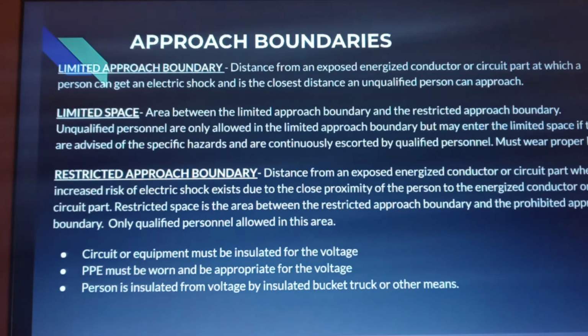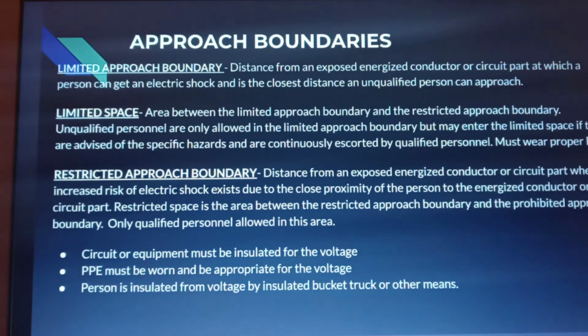The restricted approach boundary is the distance from an exposed energized conductor or circuit part where an increased risk of electrical shock exists due to the close proximity to the energized conductors or circuit parts. Restricted space is the area between the restricted approach boundary and the prohibited approach boundary. Only qualified personnel are allowed in this area, and the circuit or equipment must be insulated for the voltage inside the restricted approach boundary. PPE must be worn and be appropriate for the voltage, or a person is insulated from the voltage by an insulated bucket truck or other means.